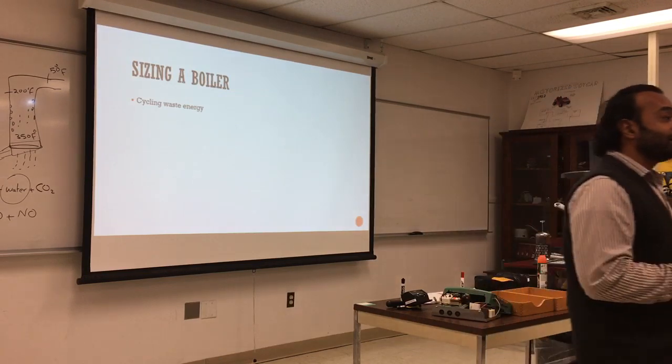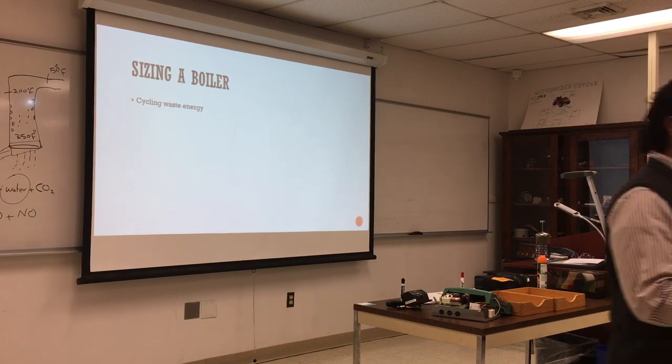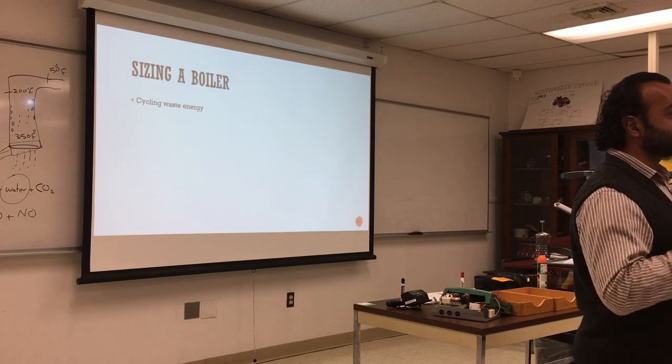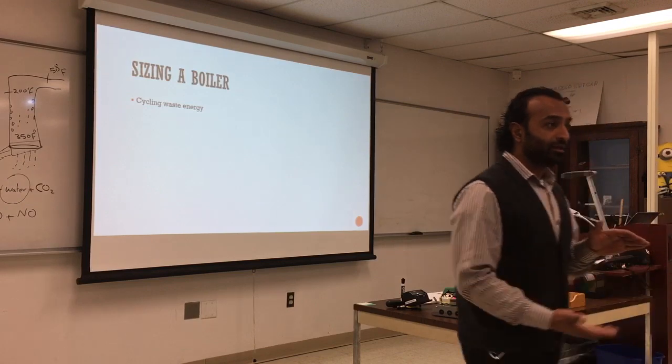Why? Let's think about it. Every time you heat the water, it's gonna go from room temperature, which is 60, to 180. Then you let it cool off completely, so you have to heat it again from 60 to 180. Meanwhile, if you keep it at 180, you have to supplement whatever you're losing in the house continuously. So this cycling does cause you to lose some efficiency.